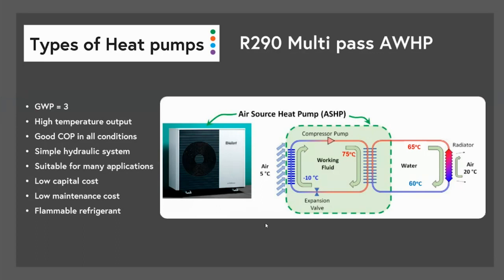The compressors on an R290 appliance are running at much lower pressures, and we'll get into a bit of detail on that later, which means that they are lower cost because they don't have to be so massive. The only other thing about R290 heat pumps is that R290 is propane, as we were talking about, and that's a flammable refrigerant, but we'll get into that a bit later as well.